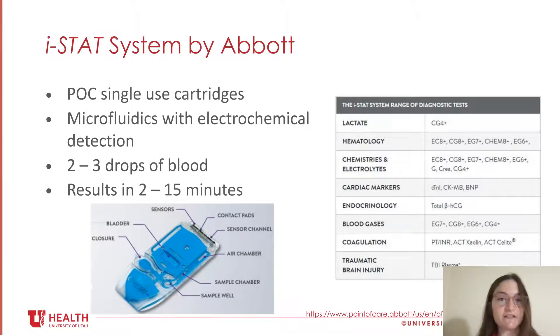An example of this technology is the iSTAT. iSTAT was one of the first commercially successful lab-on-chip-based platforms for human diagnostics. It's a single-use cartridge-based system with all analytical requirements for performing a test contained within that single cartridge: a sample entry well, a fluidic channel, a calibrant solution and reagent stored in a central bladder, thin film electrodes coated with a specific ionophore on a silicon chip, and a waste chamber. The cartridge must be placed on a portable iSTAT analyzer, which contains a motor to control the flow of calibrant and sample within the cartridge, an electrical connector to receive signals from the sensors, and an electronic system to measure and monitor those signals. These signals are transformed into quantitative results based on established calibrations.